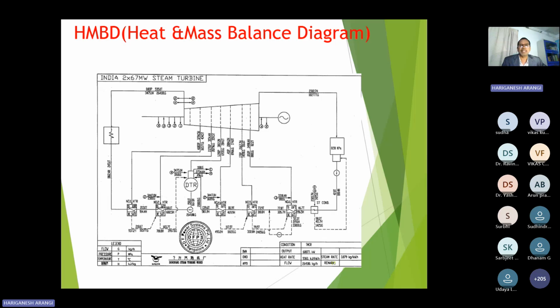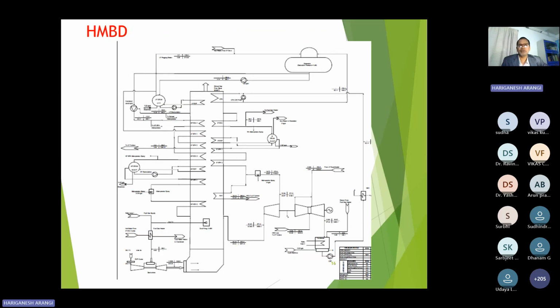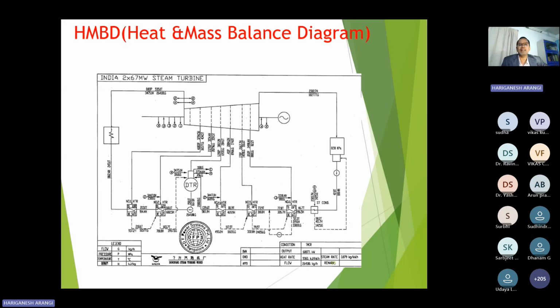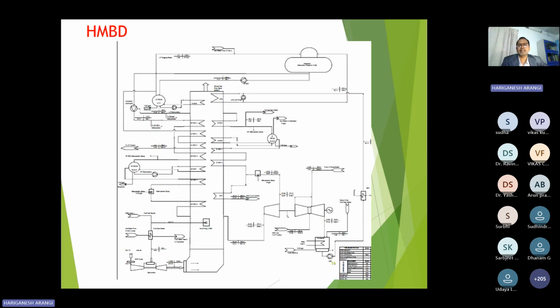Then what we have discussed, the HMB, heat and mass balance diagram. This is typical, showing how many megawatts we are going to generate. The previous one was for the steam turbine plant, the coal plant, and this is the combined cycle plant. In this heat mass balance diagram, at the bottom left is the gas turbine area, and this tall rectangle you are looking at is the HRSG, heat recovery steam generator. From there, steam will go to the right side, which is the steam turbine area.